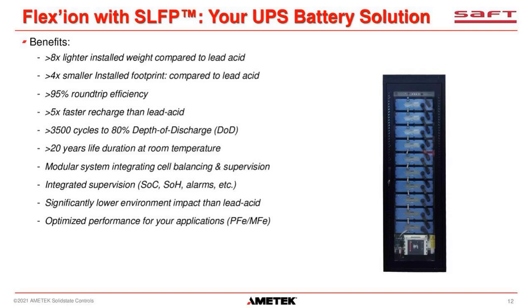The Flexion battery is rated for over 3,500 cycles to 80% depth of discharge, and has a 20-year lifespan at room temperature. And since it's a modular system, you can replace a single battery module if it fails, and the BMM has integrated cell balancing and supervision. The BMM also provides state of charge, state of health, alarms, voltages, currents, and other things too.